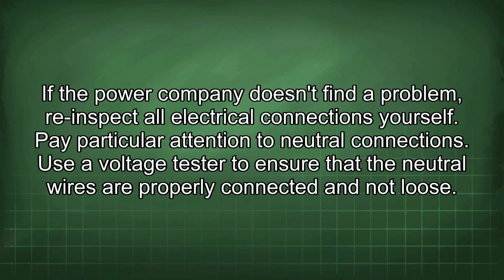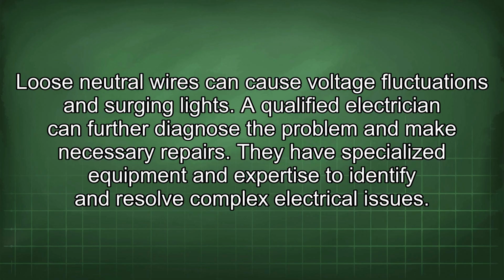If the power company doesn't find a problem, re-inspect all electrical connections yourself. Pay particular attention to neutral connections. Use a voltage tester to ensure that the neutral wires are properly connected and not loose. Loose neutral wires can cause voltage fluctuations and surging lights. A qualified electrician can further diagnose the problem and make necessary repairs. They have specialized equipment and expertise to identify and resolve complex electrical issues.